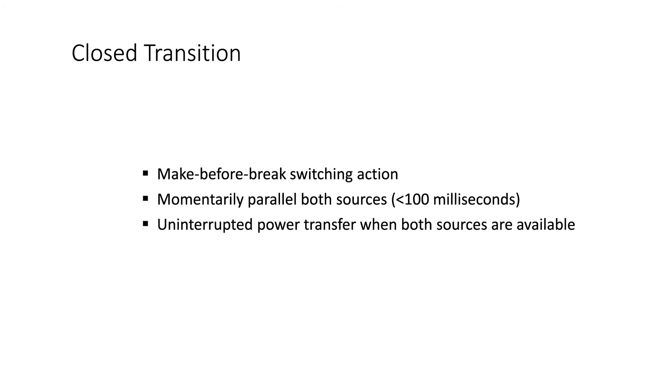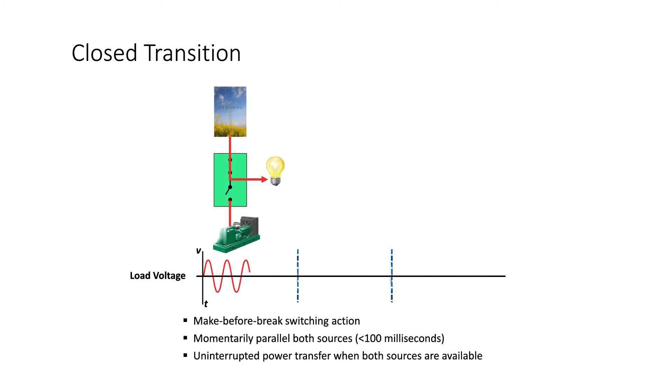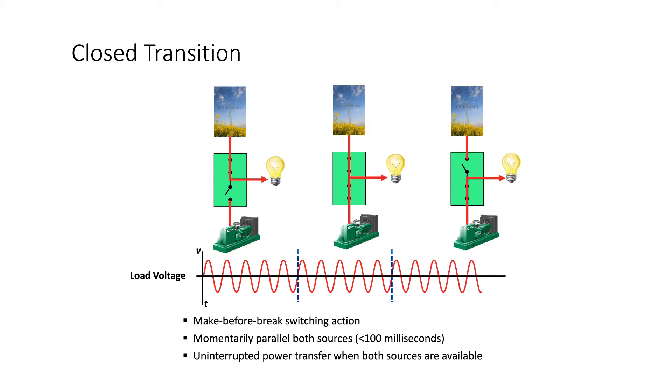Finally, closed transition transfer, also known as make-before-break, offers uninterrupted transfer of the load by momentarily paralleling between both live sources for less than 100 milliseconds. Therefore, there is no power interruption to the load.